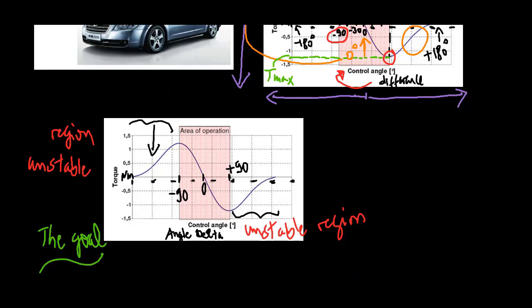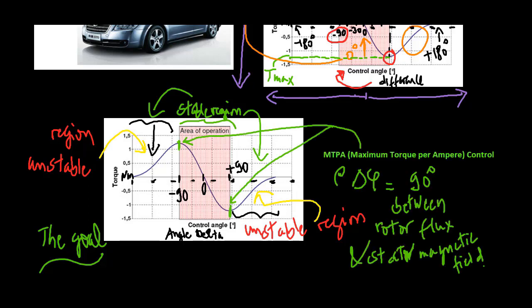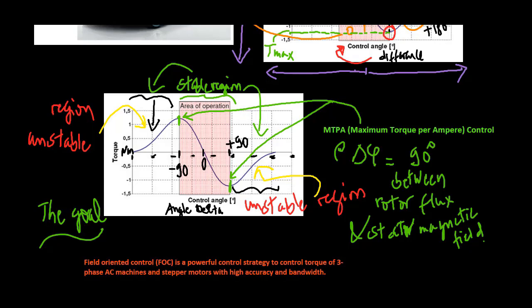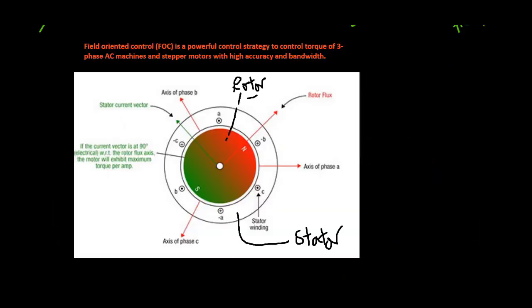The goal is obviously to not let the motor get over the stable region, because this part of the region is unstable. At the top of that curve is where we get maximum torque per ampere, and that's what field oriented control is going to allow us to do — and to allow us to do it in a stable way, so that we don't have to worry about coming out of the stable region.